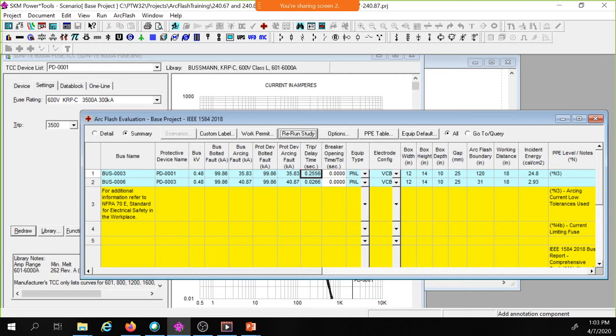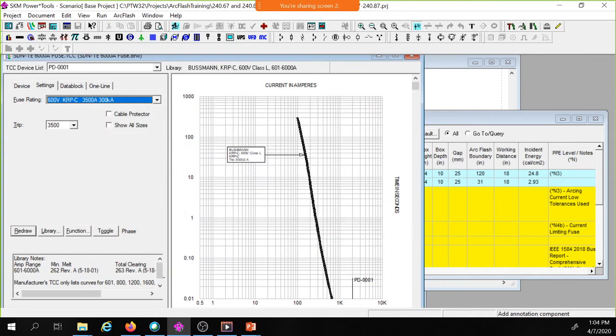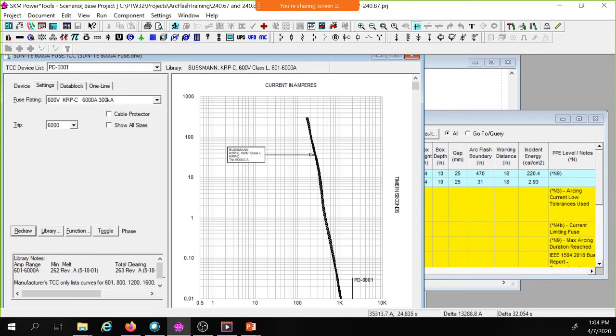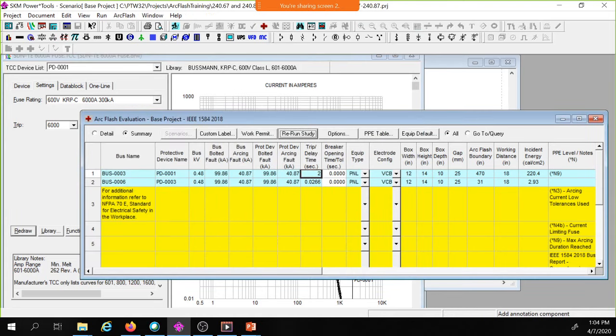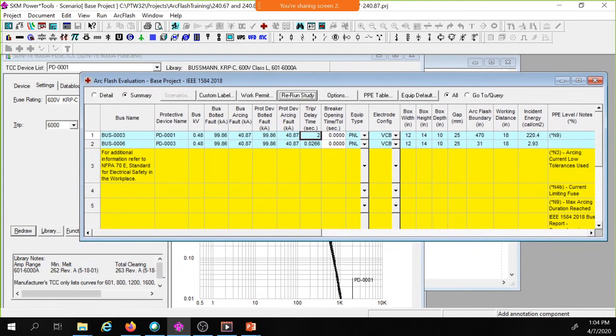This is beyond the 0.07 mark. That's why you have this number right here. My incident energy for a clearing time of 0.2 seconds is 24.8. This is for approximately 100,000 amps of fault current. I'm going to move this to the largest class fuse, a 6,000 amp fuse. I'm up to 220.4 calories. My clearing time is longer than 2 seconds.